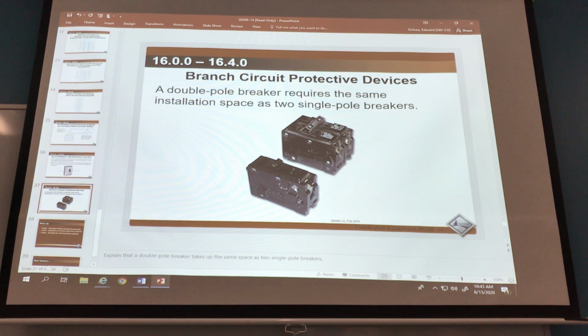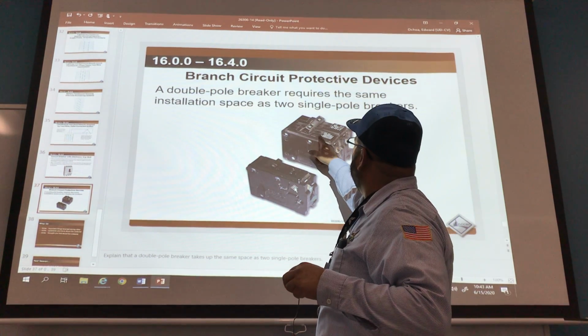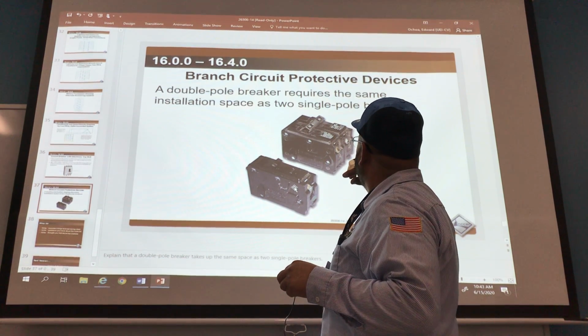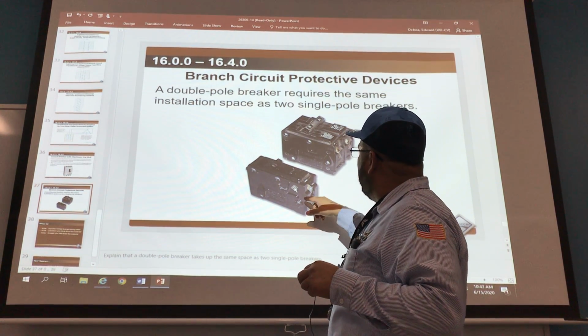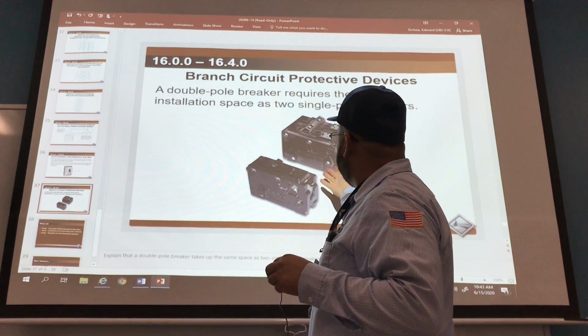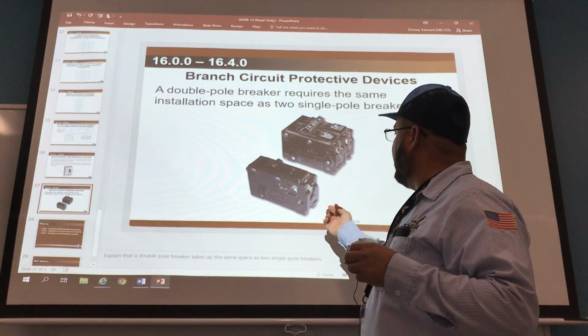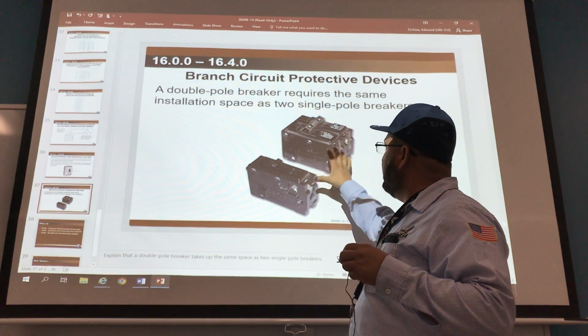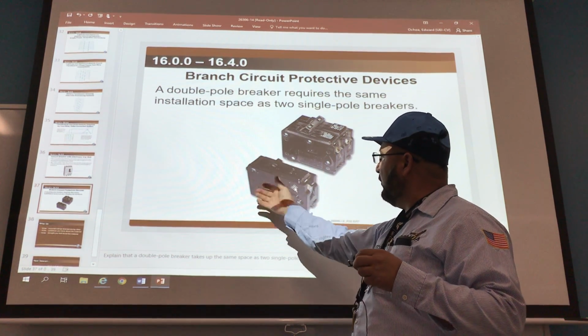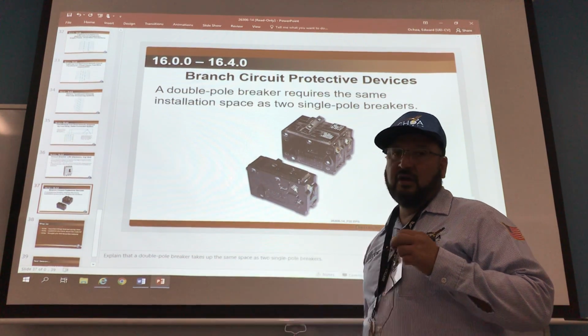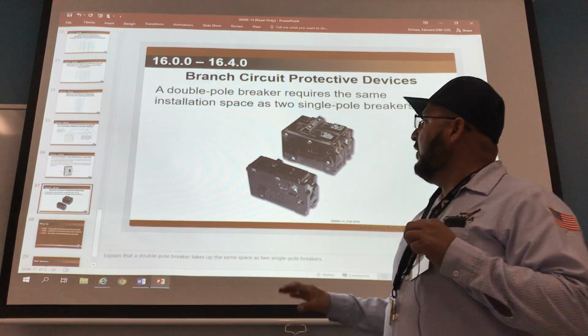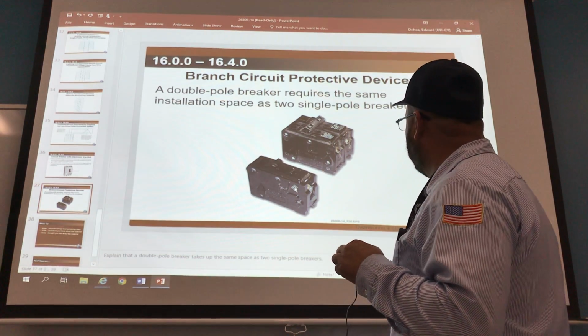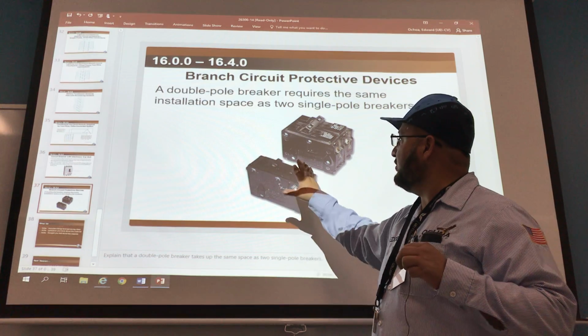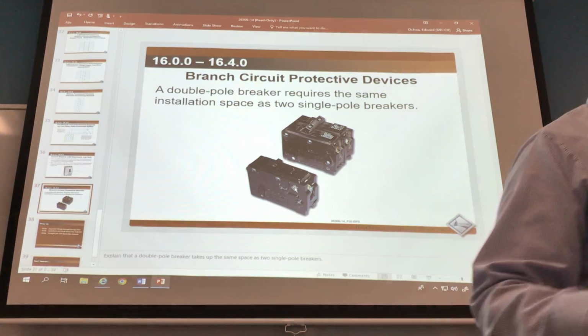Branch circuits, same thing. The branch circuit breakers. Looks like this is some Murray. Anyway, they're actually two different styles, but this is just a typical breaker. Power comes in. Always, when you look at these breakers, you've got to look at the footprint. Flip it over, look at the footprint, see how it's connected. Look at your power panel, see how it's landed in there. Always identify your panel. It's very important to match your panel to the breakers because there could be two different items, and that's not good.